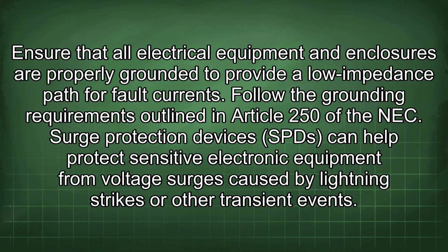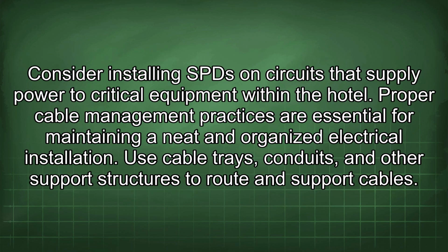Grounding is another critical aspect of electrical safety. Ensure that all electrical equipment and enclosures are properly grounded to provide a low impedance path for fault currents. Follow the grounding requirements outlined in Article 250 of the NEC. Surge protection devices (SPD) can help protect sensitive electronic equipment from voltage surges caused by lightning strikes or other transient events. Consider installing SPD on circuits that supply power to critical equipment within the hotel.